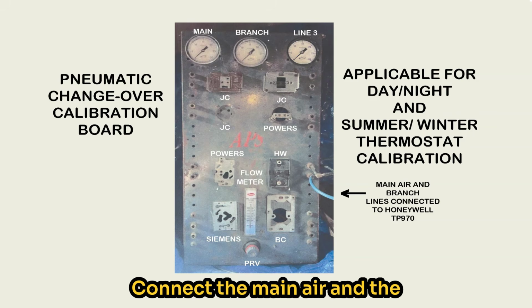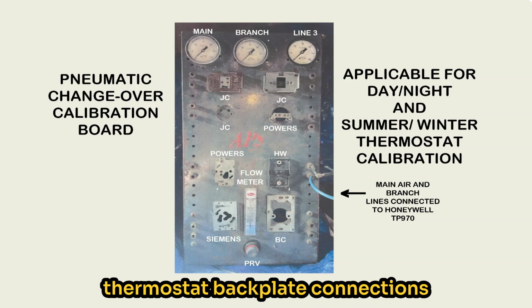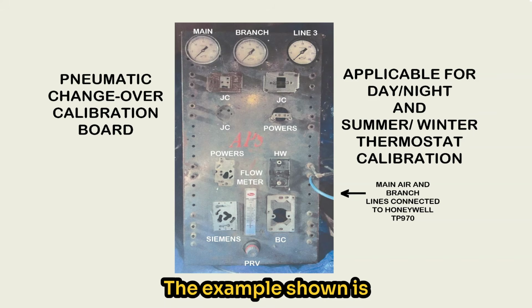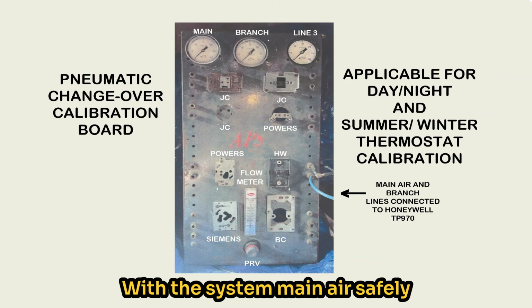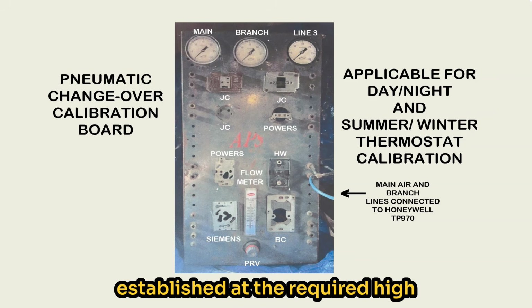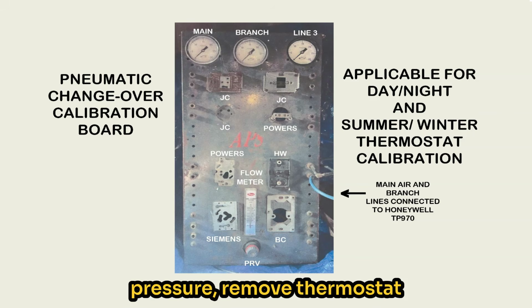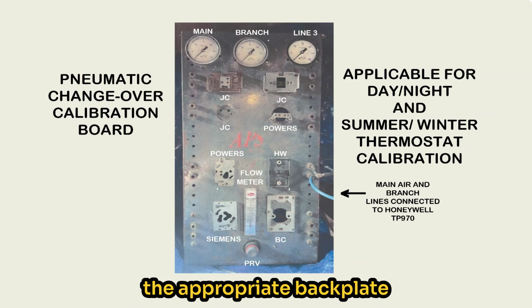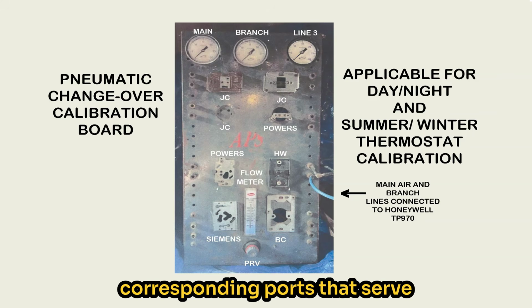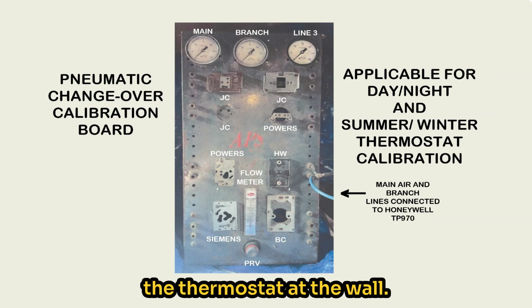Connect the main air and the branch lines to the appropriate thermostat backplate connections on the calibration board. The example shown is configured for the TP970. With the system main air safely established at the required high pressure, remove the thermostat from the wall and install it on the appropriate backplate on the calibration board. Connect the main air and the branch lines to the corresponding ports that serve the thermostat at the wall.